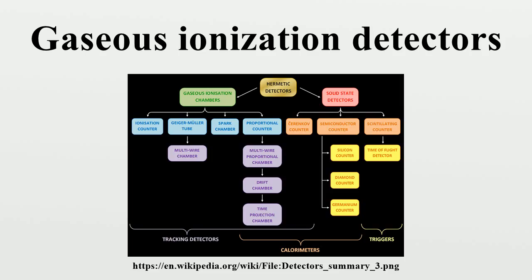The three basic types of gaseous ionization detectors are ionization chambers, proportional counters, and Geiger-Müller tubes. All of these have the same basic design of two electrodes separated by air or a special fill gas, but each uses a different method to measure the total number of ion pairs that are collected. The strength of the electric field between the electrodes and the type and pressure of the fill gas determines the detector's response to ionizing radiation.